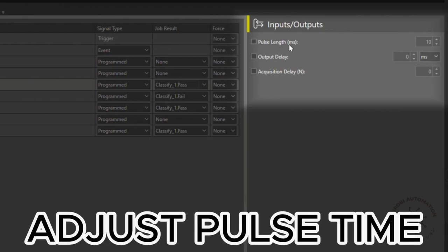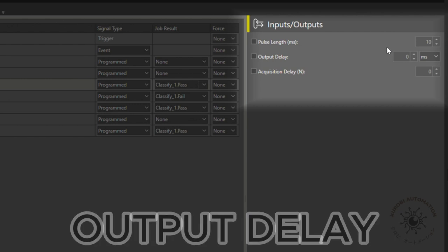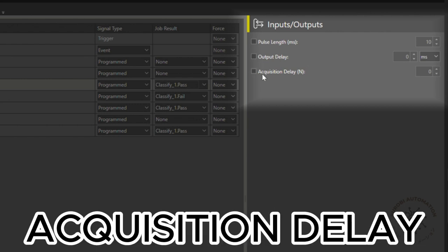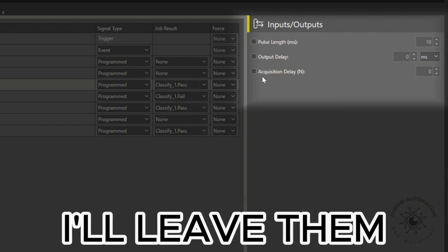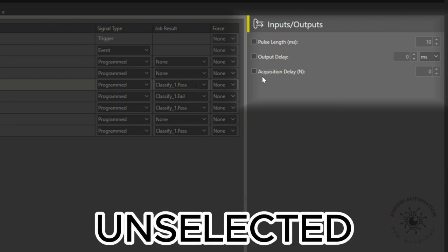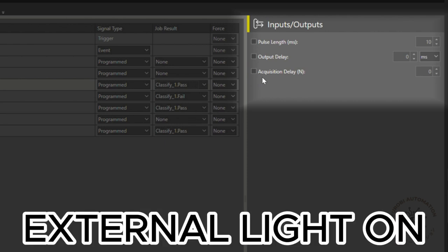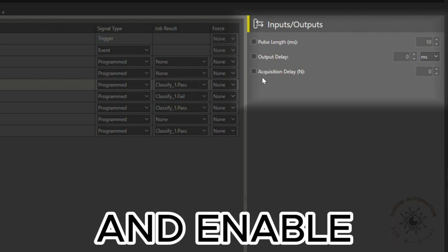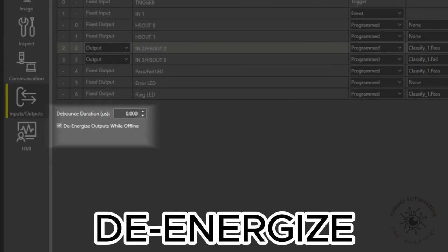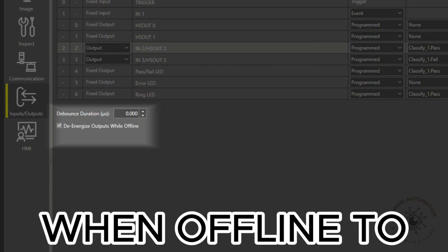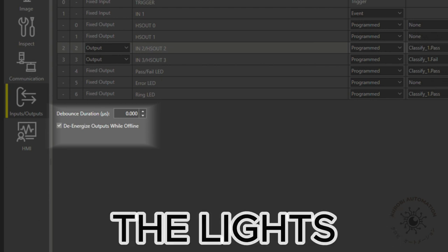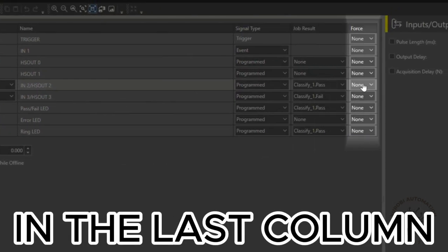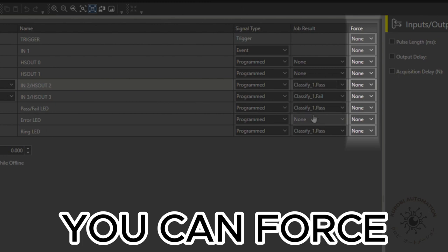To the right, adjust pulse time, output delay, and acquisition delay. I'll leave them unselected to keep the external light on and enable de-energize when offline to turn off the lights when the system is offline. In the last column, you can force the signal on and off.